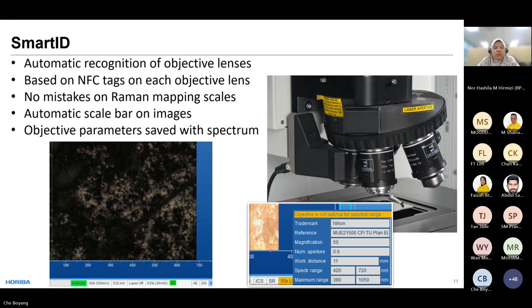But now on the latest model, we have this function called Smart ID. On each objective lens, we have an NFC tag, and we have an NFC tag reader to read each tag. So every time you change the objective lens, the reader will know, the software will reflect that, and it will change the scale bar accordingly. So you will never make a mistake on the scale bar of your result.